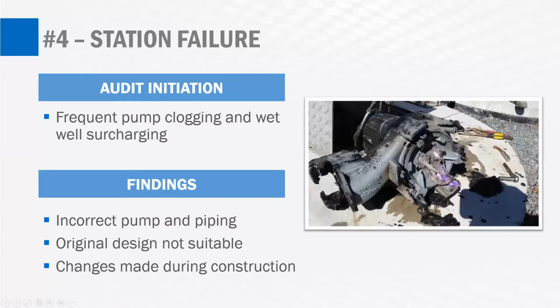So for the fourth and last case study for today, we're going to talk about a station that, in my mind, I like to call the complete station failure. Basically, this station suffered from start to end, from planning all the way through to the operation and maintenance stages. The audit was initiated because this station was frequently clogging. There was significant wet well surcharging to the point that the owner was worried of an SSO occurring at this station, which was right next to protected wetlands. So it was a scary situation that needed to be addressed.